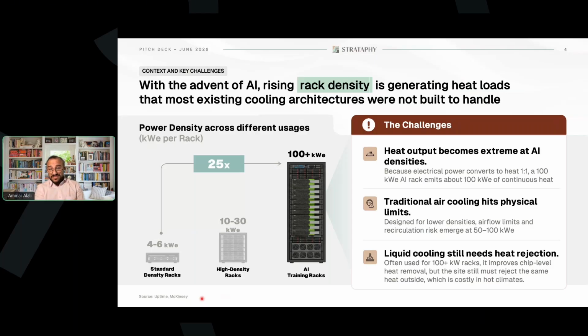The growth in this space is significant. They used to have 1 rack in the same footprint roughly 5 kilowatt. We started to see 25 kilowatt, and earlier last year we started to see 100 kilowatt. Today, data center construction and design companies are looking at 250 kilowatt. NVIDIA is even talking about a potential rack that could sustain 1 megawatt. That's a significant 2 magnitude higher growth in energy for the same footprint for the rack and the data center.